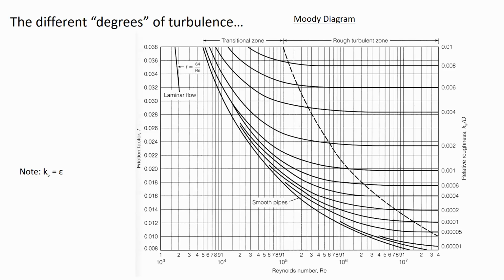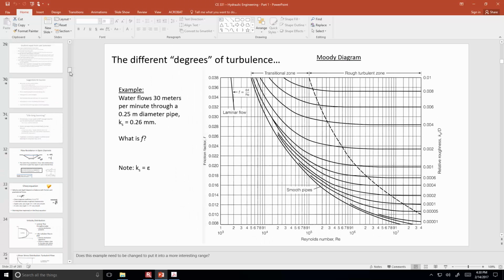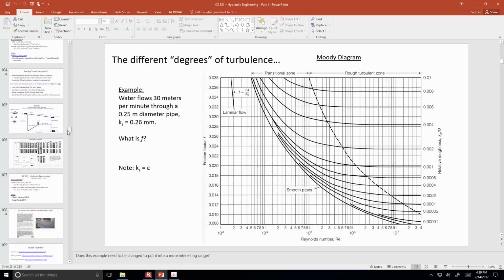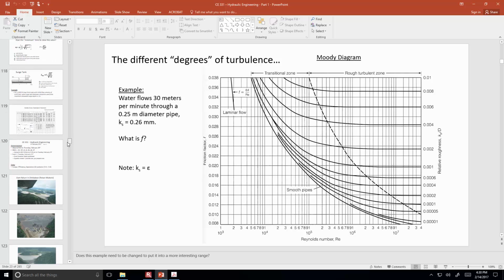So here's that. I know I'm going to be okay if it's in the relatively flat part of the curve. This is the fully turbulent segment, and I'm just right at the beginning of that. If I go over, it's basically slightly below the 0.02 line, so I'm calling that one good enough. But the people who actually ran the numbers in the Jain equation are saying that the f value was maybe about 1.5% different. And so, heck, if you're setting this up electronically or you don't mind doing the hand calculations, by all means, do the second iteration. But just for purposes of illustration, where you're learning how to set the pump curve equal to the system curve, I think that we can call this one converged. That would be the flow rate.